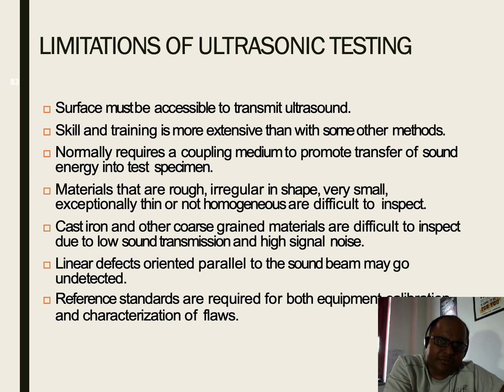Surface must be accessible to transmit ultrasound. Skill and training are more extensive than with some other methods. It normally requires a coupling medium to promote the transfer of sound energy into the test specimen. Materials that are rough, irregular in shape, very small, exceptionally thin, or not homogeneous are difficult to inspect.